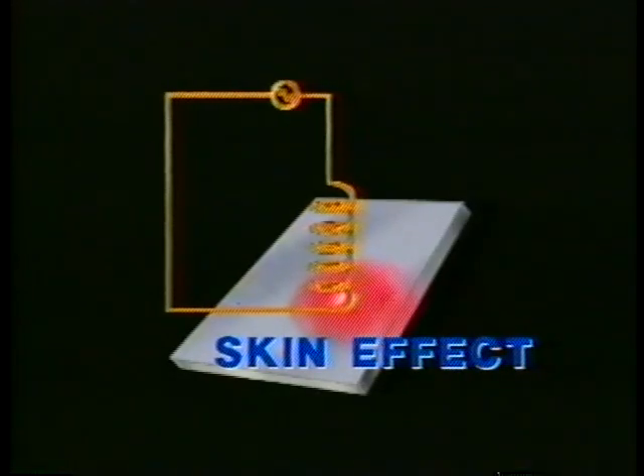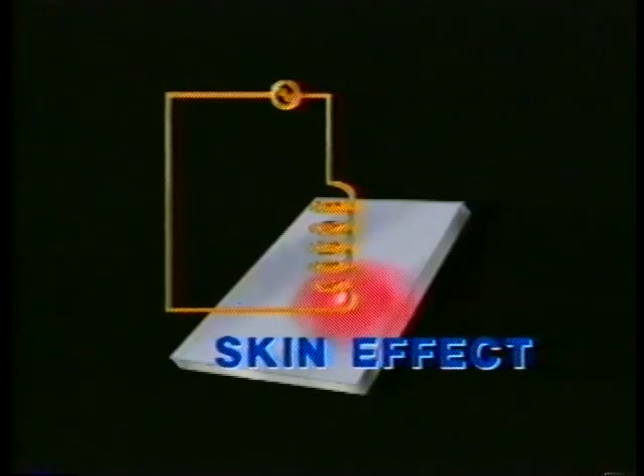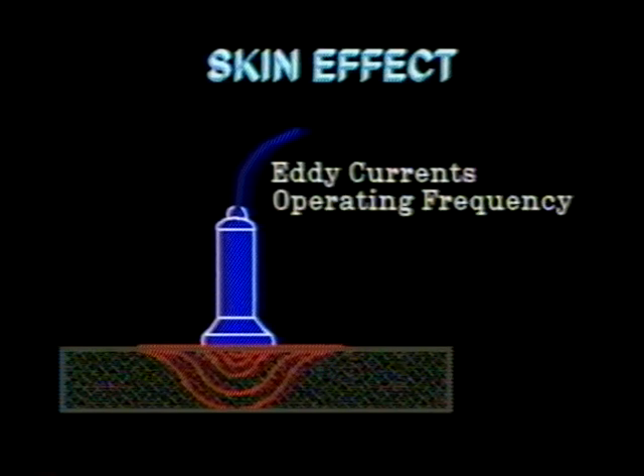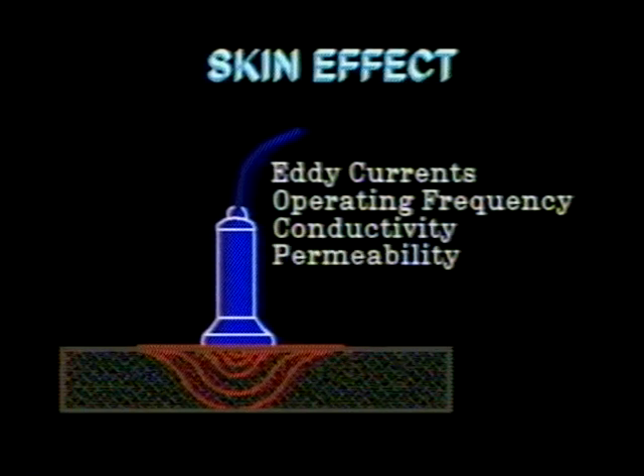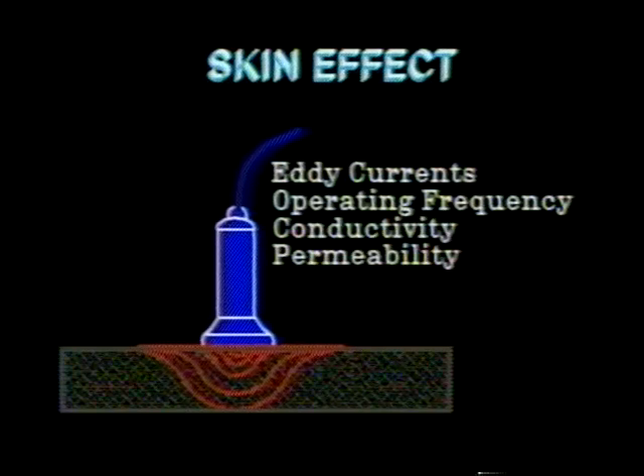In many applications, electromagnetic tests are most sensitive to test object variables nearest the test coil. This is due to skin effect. Skin effect is a result of interaction between eddy currents, operating frequency, test object conductivity, and permeability. The skin effect is the concentration of eddy currents nearest the test coil, and becomes more evident as test frequency, test object conductivity, and permeability are increased.